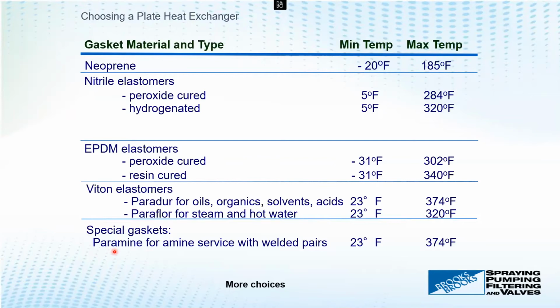We keep the amine between the welded plates and use paramine gaskets on whichever side they prefer. I mentioned 400 degrees as a rule of thumb, just because I can remember it, but 375 is really the top end of temperature that most elastomeric gaskets can take, certainly for heat exchangers.